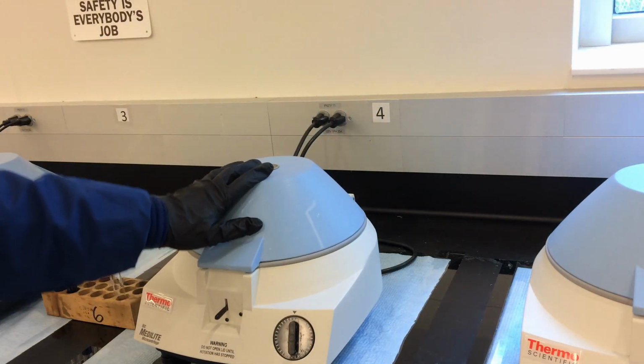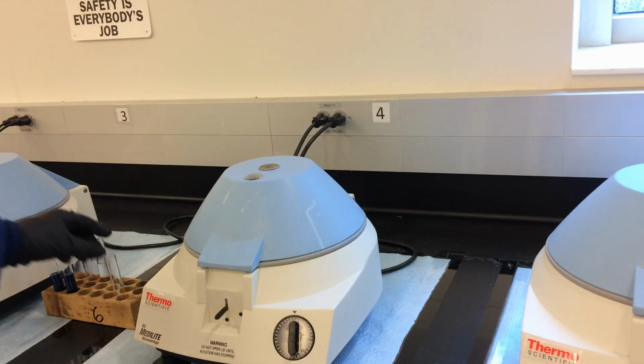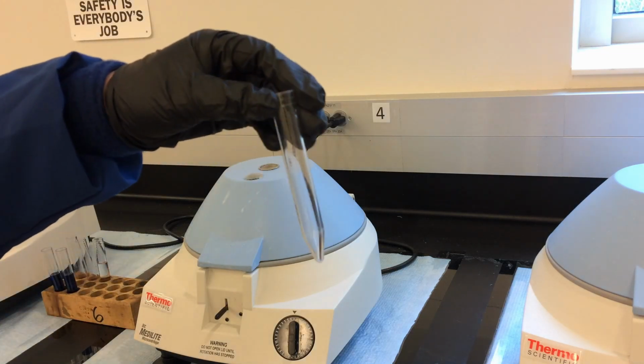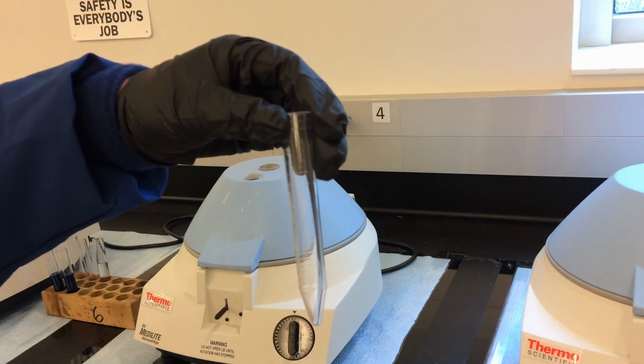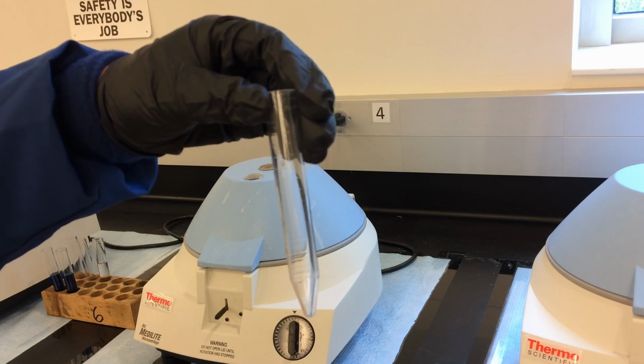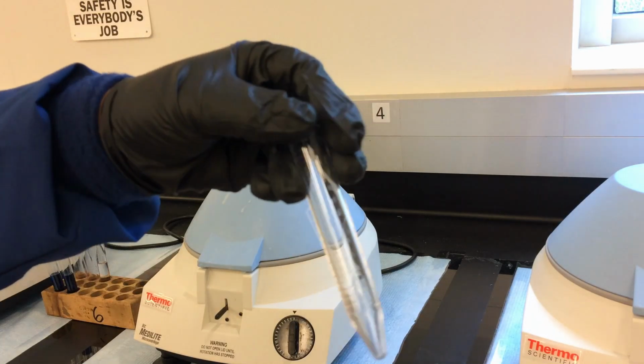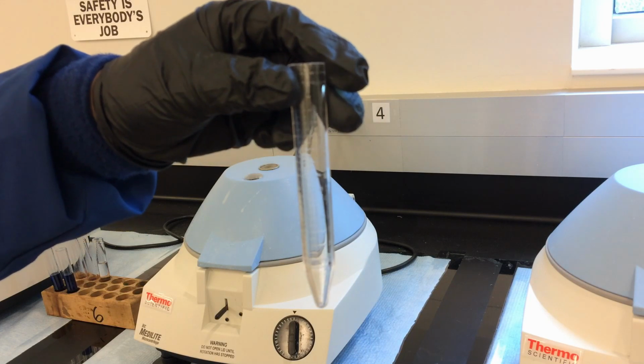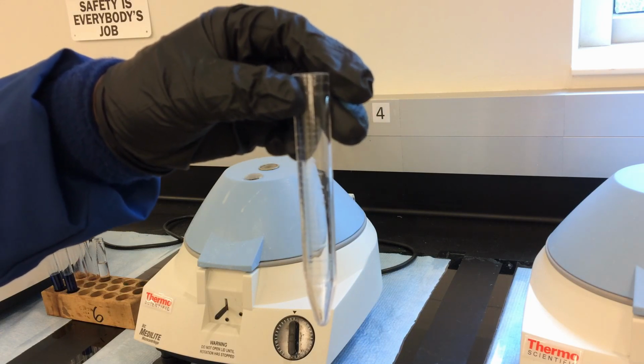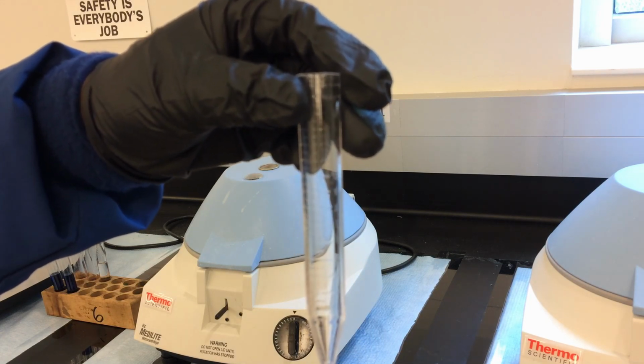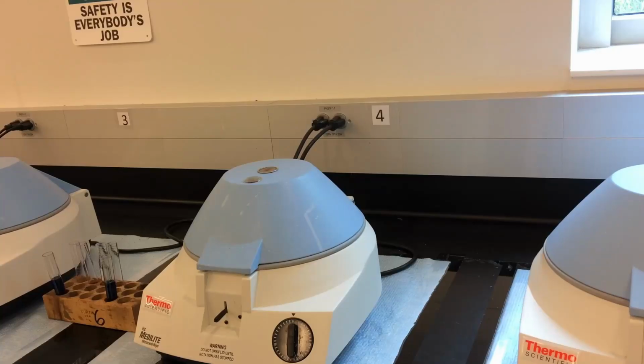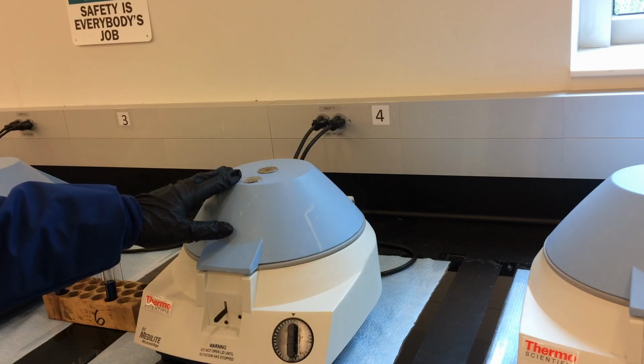To use this centrifuge, you should use this type of centrifuge tube provided by the stockroom. It is plastic. Do not use other tubes in your bin, for example, glass test tubes. One of the most important things about using a centrifuge safely is that it must be balanced to prevent vibration.